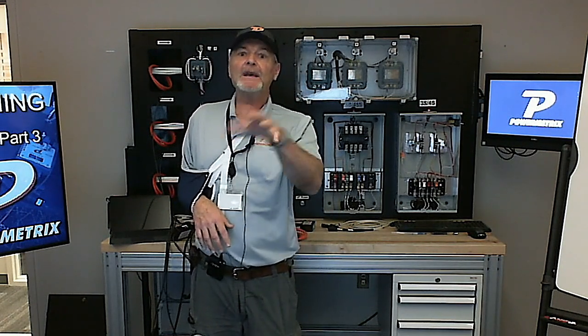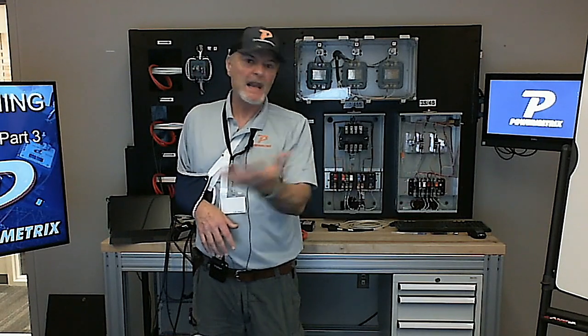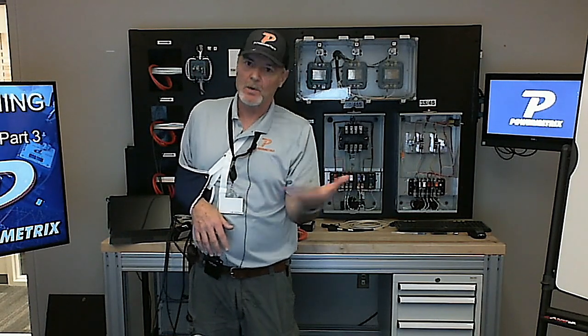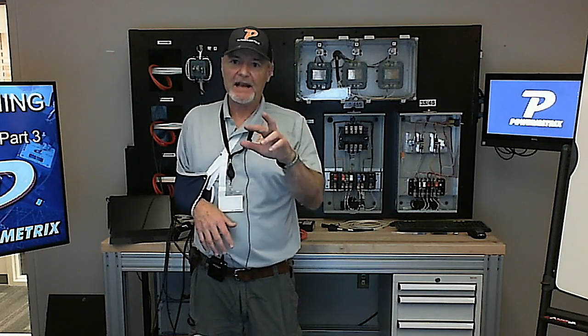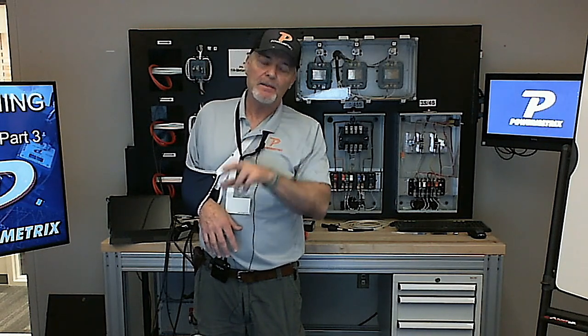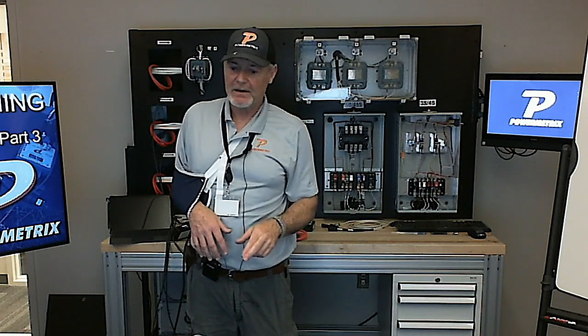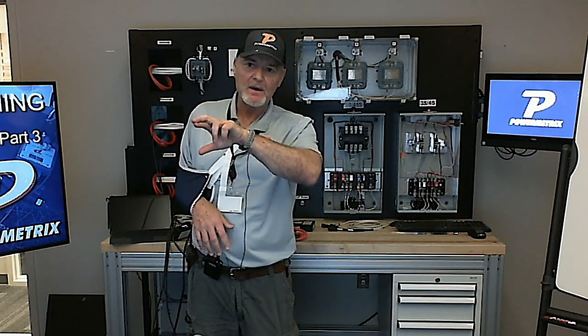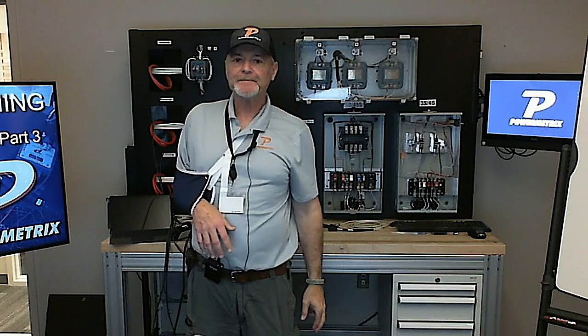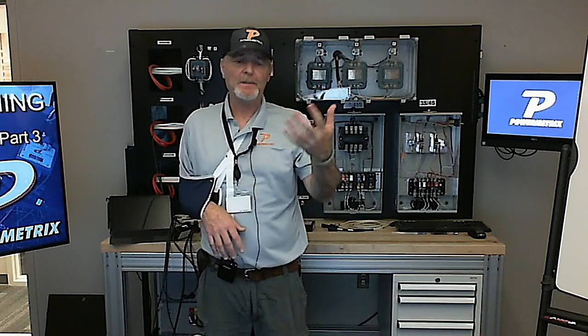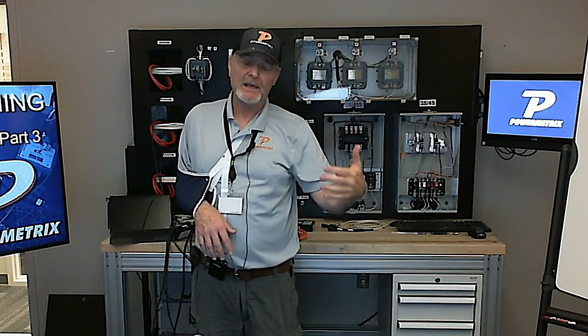So it showed us that we should have been on B phase for the voltage, and we were, and everything worked out okay. There's also the meter view, which is what it defaults to, and you're going to see what the meter's seeing - same thing the meter's seeing after it does its work internally. So in that case, it had a VAB because it was relating A to B - it had A and B paired up together. So you can see it'll have a VAB on there. If you see more than one letter on there for phases, then you know it's using another phase as a reference. Otherwise, it would be very clean and be VA, VB, VC, IA, IB, IC.